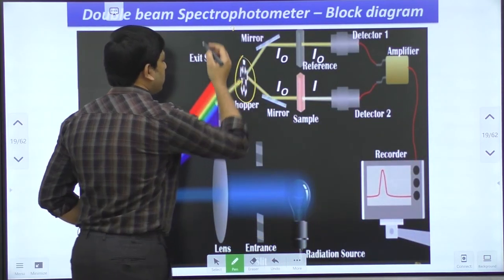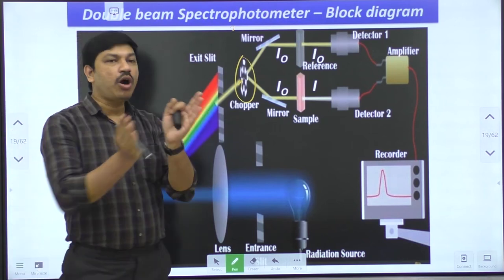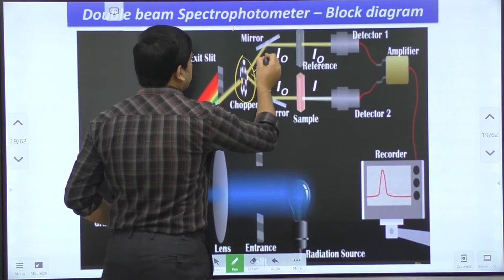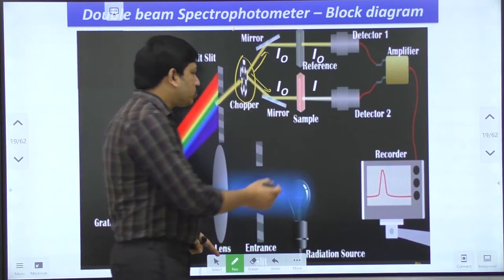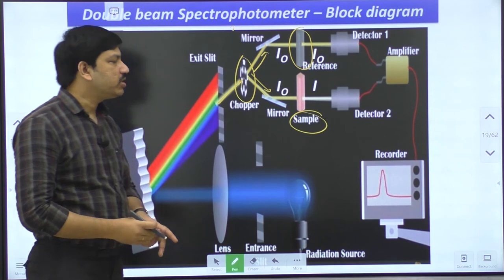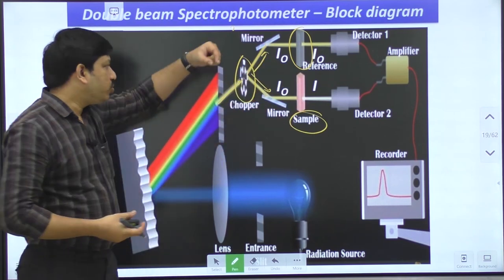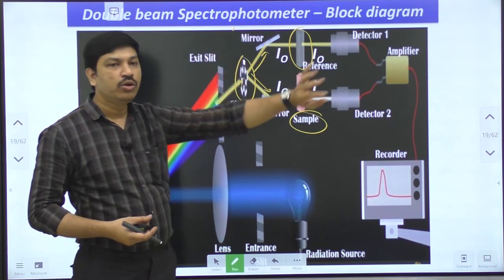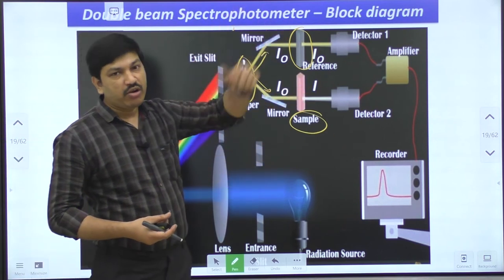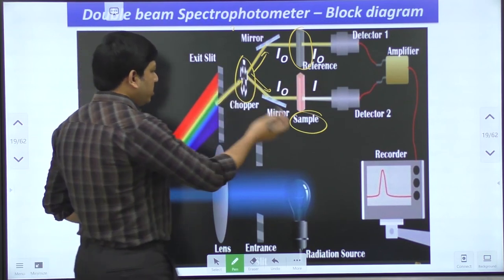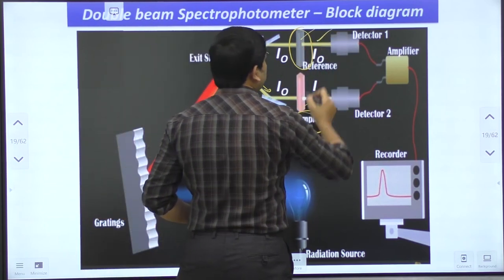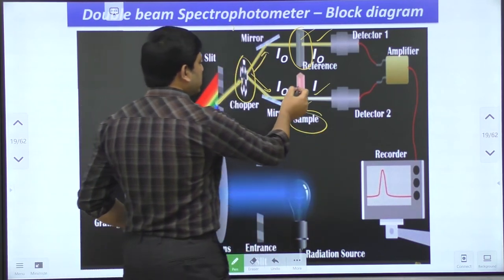Before reaching the sample, the radiation goes to a chopper. The chopper cuts the single radiation beam into two halves, converting it into two different beams. One beam goes to the unknown sample and the other goes to the reference compound. This means in the double beam technique, we can simultaneously use a reference compound and a sample compound — there is no need for two separate measurements as in the single beam spectrophotometer.